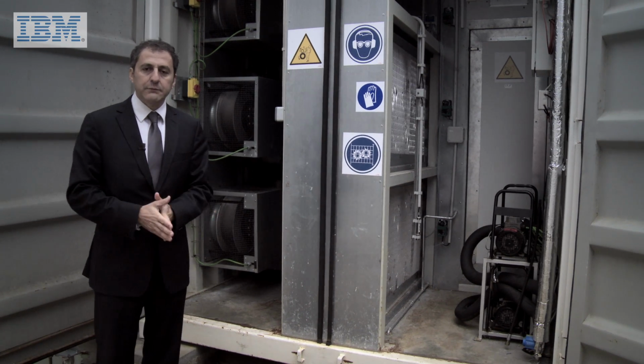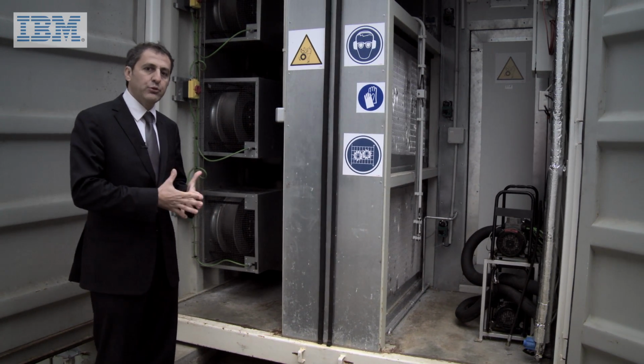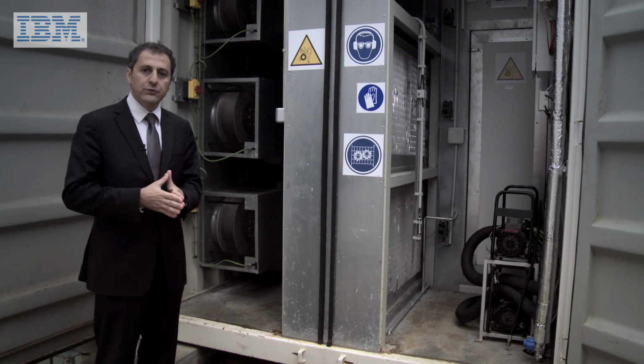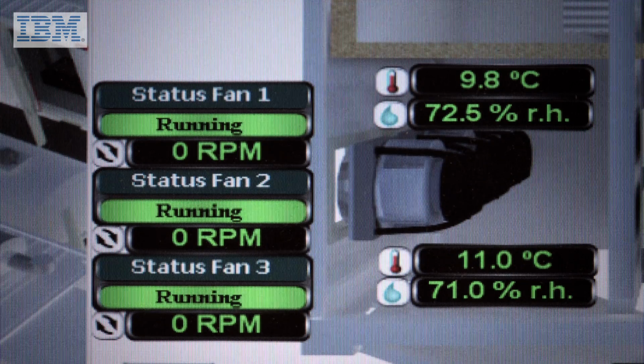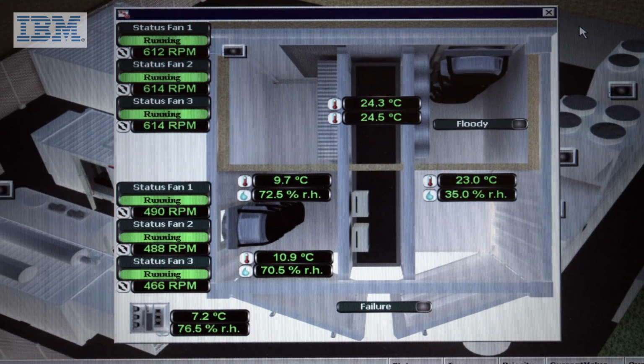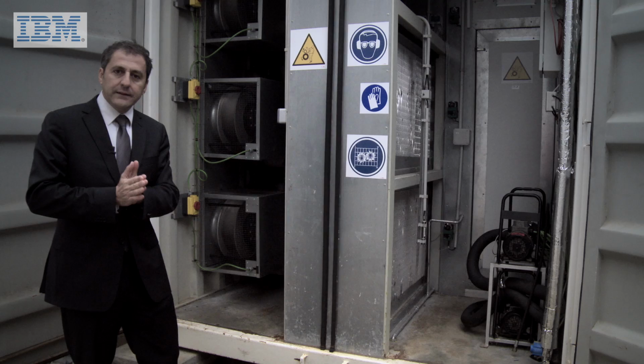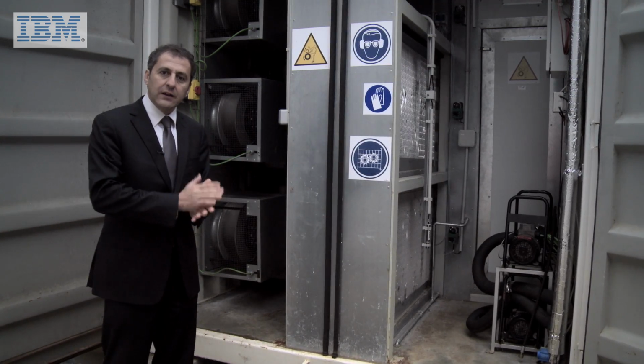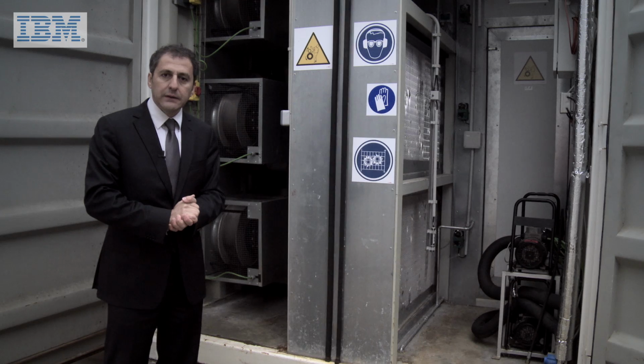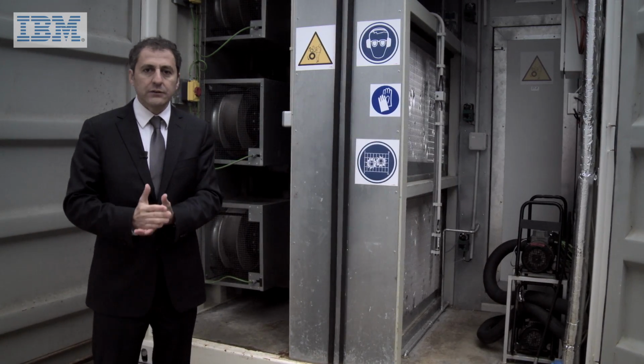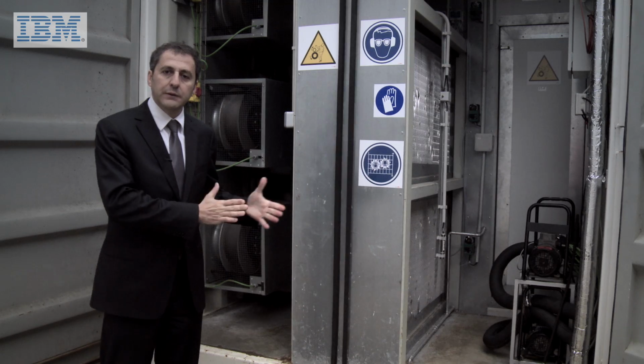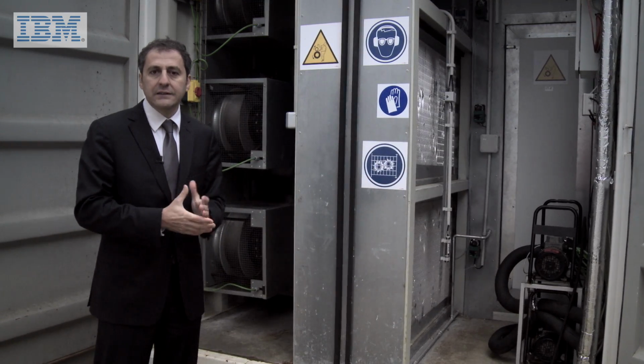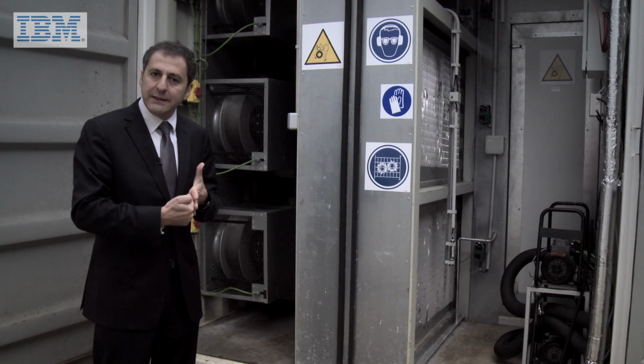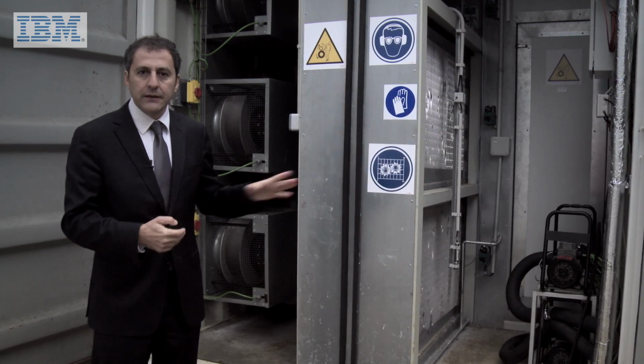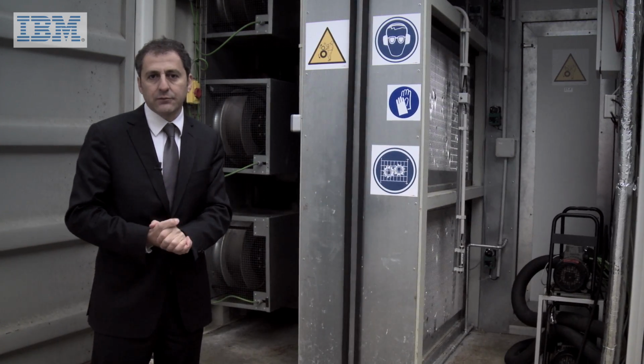This is the natural free cooling module, which is attached to the IT modules and provides cooling in a very energy efficient way. This is driven by EC fans and a heat exchanger, which has all the benefits of direct free cooling, but we prevent the risks of bringing external air into the IT room, and we prevent any risk associated with pollution or fire or smoke coming into the room, since we preserve the IT area totally independent from the external air. This is thanks to this heat exchanger, as I explained.